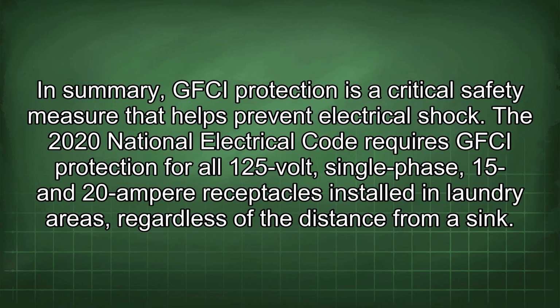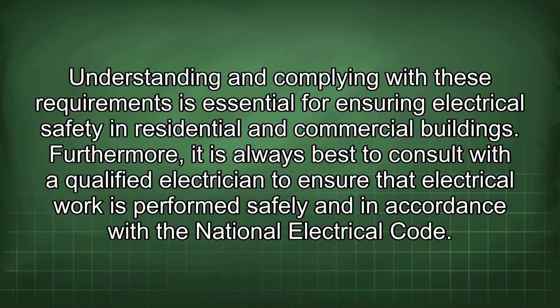In summary, GFCI protection is a critical safety measure that helps prevent electrical shock. The 2020 National Electrical Code requires GFCI protection for all 125-volt single-phase, 15 and 20 ampere receptacles installed in laundry areas, regardless of the distance from a sink. Understanding and complying with these requirements is essential for ensuring electrical safety in residential and commercial buildings.